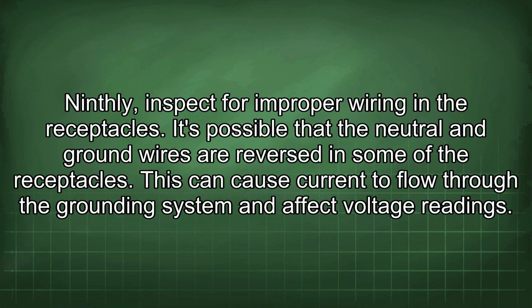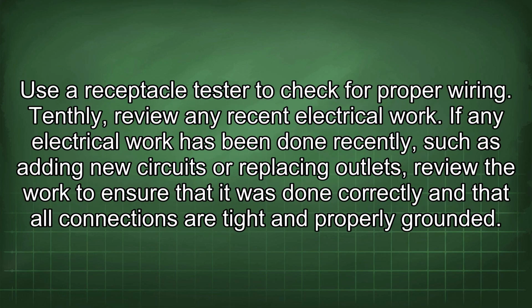Ninthly, inspect for improper wiring in the receptacles. It's possible that the neutral and ground wires are reversed in some of the receptacles. This can cause current to flow through the grounding system and affect voltage readings. Use a receptacle tester to check for proper wiring. Tenthly, review any recent electrical work. If any electrical work has been done recently, such as adding new circuits or replacing outlets, review the work to ensure that it was done correctly and that all connections are tight and properly grounded.